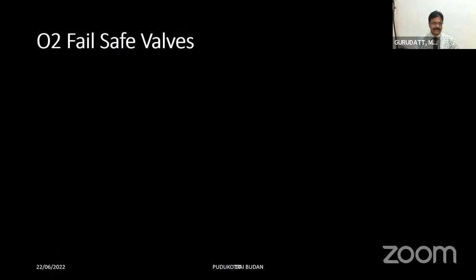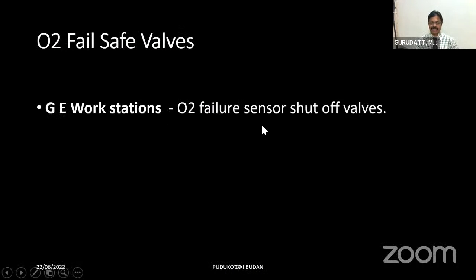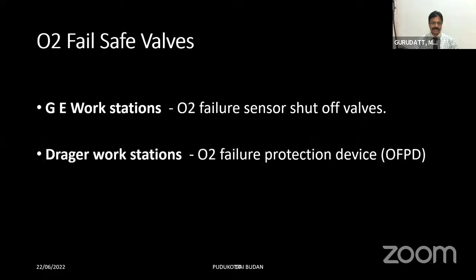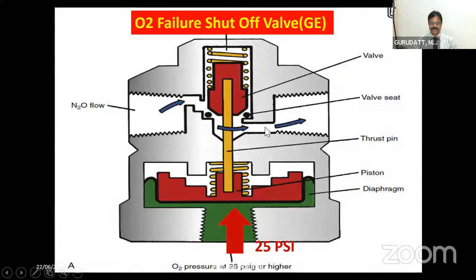In GE machines, they are called as oxygen failure sensor shut-off valves. That means they are all or none. Either the flow of nitrous oxide is there or flow of nitrous oxide is cut off at a particular critical pressure of oxygen. Whereas in Draeger workstations, what we have is oxygen failure protection devices. So they are slightly different. Let me discuss about the shut-off valves first, that is present in the GE workstations.